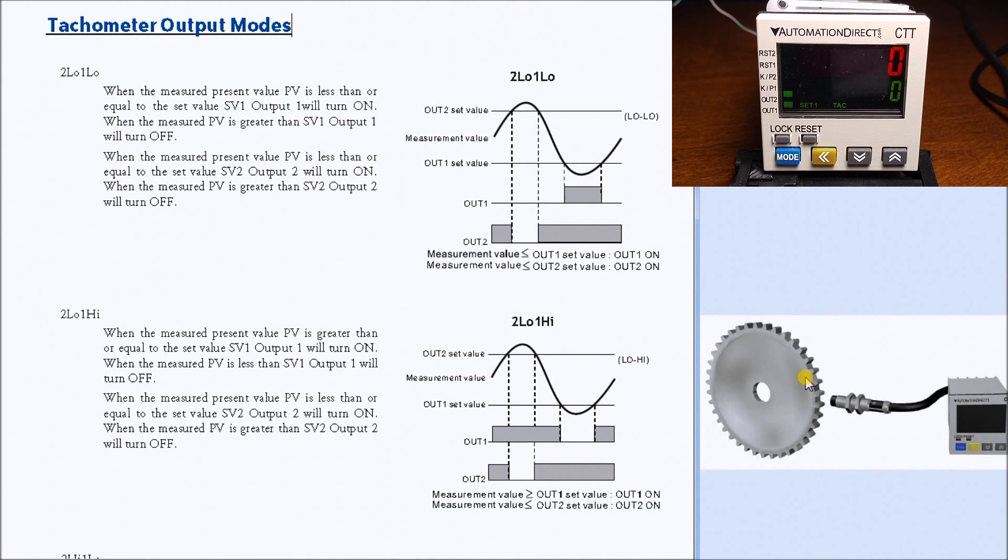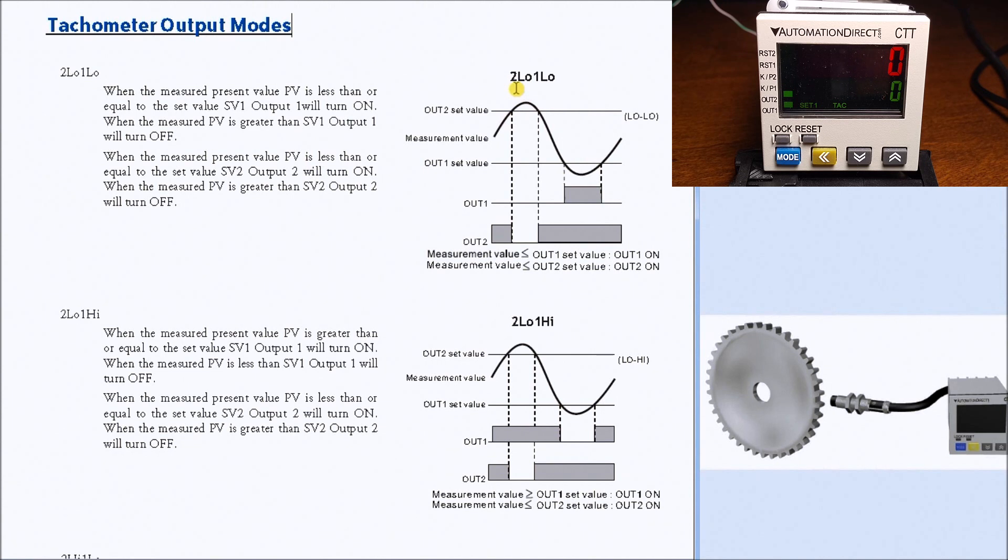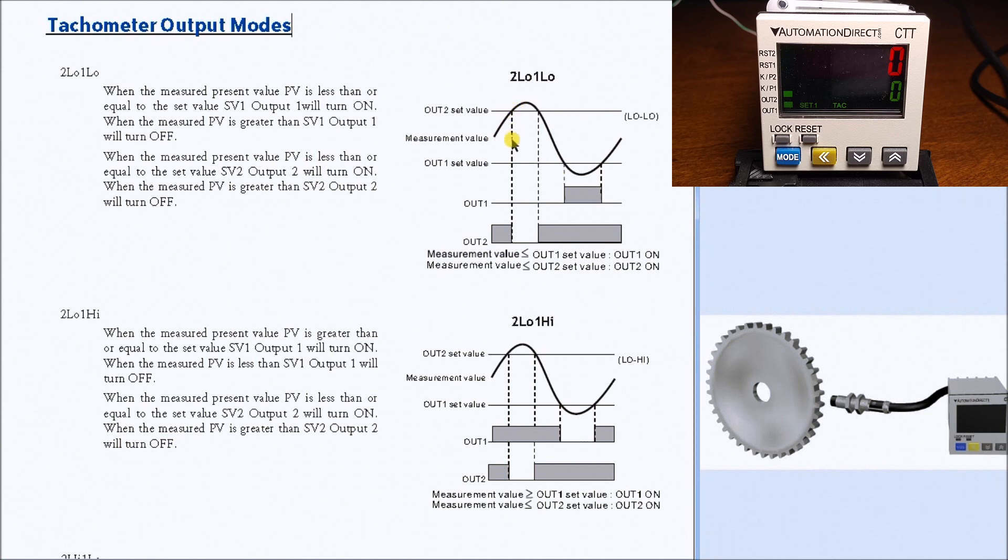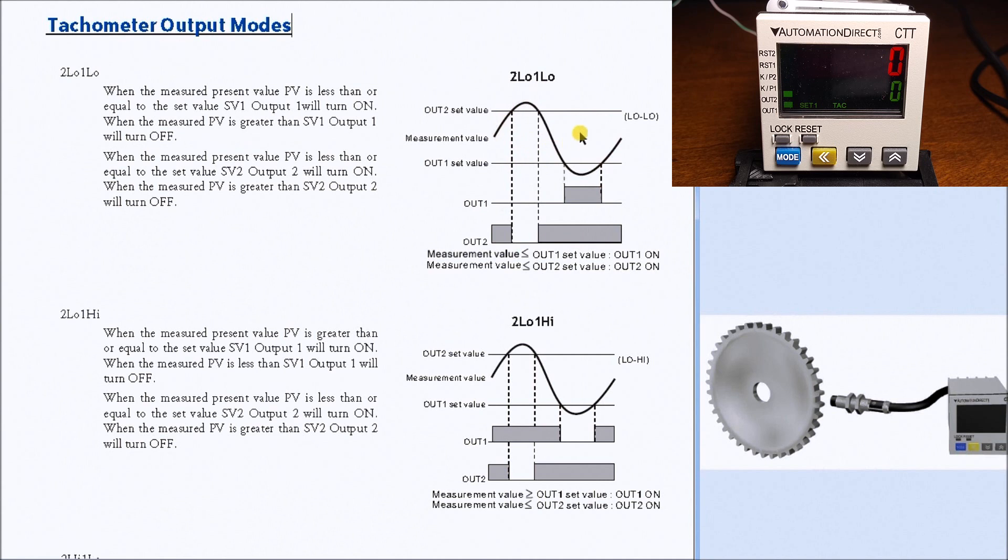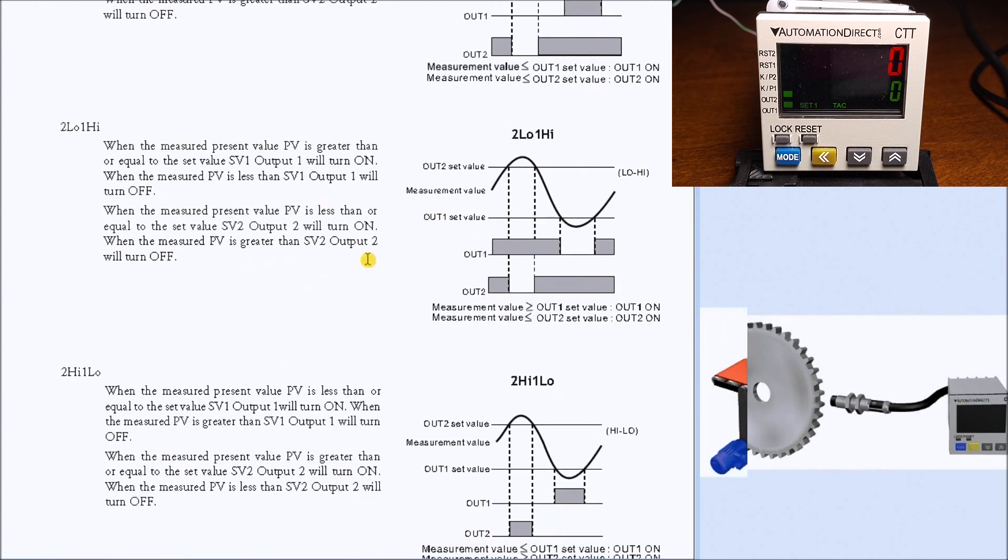We have four different output modes for this tachometer. You can see from the timing chart the first one is 2-low 1-low, meaning output contact 2 turns on if it's lower than the set value, and output 1-low turns on if it's lower than that. This creates an area in which both units are on.